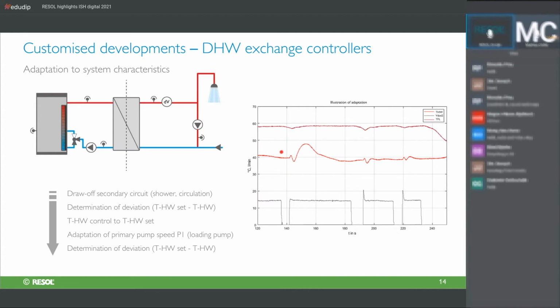In this case, the hot water temperature, or the set point of the hot water temperature, is around 40 degrees Celsius, and the flow temperature on the primary side is around 60 degrees here. What can be seen now is that after the tapping is stopped and started again, the hot water temperature swings a little bit in this area here. And this fluctuation is what you feel in the shower, and what we don't want to have. Honestly, it is not possible to eliminate it completely, but we try to optimize and to minimize this fluctuation as much as possible. And as you can see, we managed to do this pretty good with our adaptation.